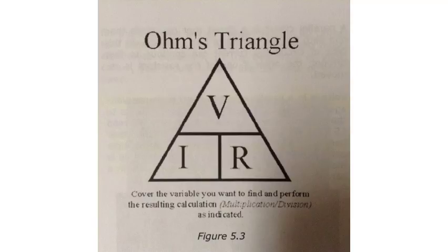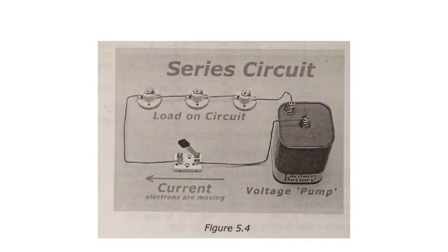Troubleshooting a series circuit is best done with a voltage meter. One thing to remember is most series circuit faults will have an open in the circuit. When an open occurs in a circuit, you will read ET, total voltage, across the open. An open is a break in the path for current to flow. The best instrument to troubleshoot a series circuit is a voltmeter.